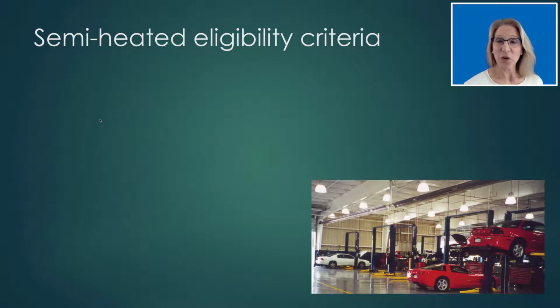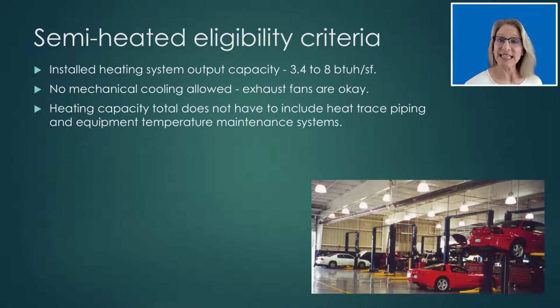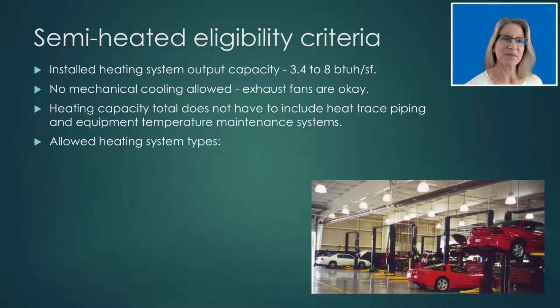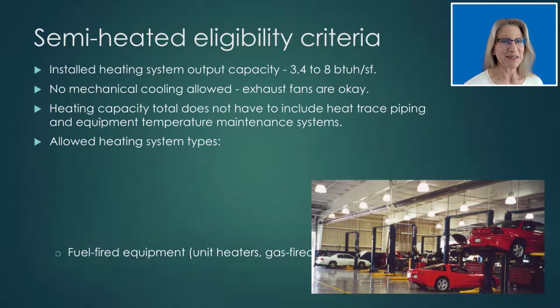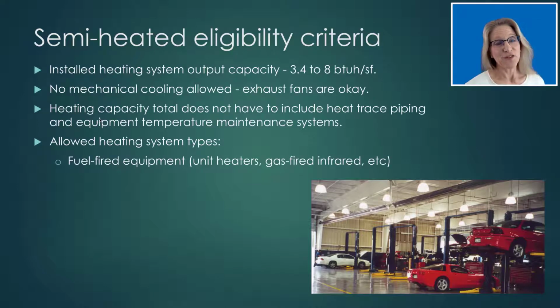So the primary basis for qualifying as a semi-heated space is that the heating system output capacity cannot exceed 8 BTUs per square foot and that there is no mechanical cooling installed. From there, it depends on the type of mechanical system that's going to be provided to serve the space. So there are some changes to the types of heating systems that are now allowed to serve a semi-heated space. So you can have a fuel-fired equipment type. The typical ones that we see often in semi-heated spaces are unit heaters and gas-fired infrared heaters, that kind of thing, and that is not a change in the new code.